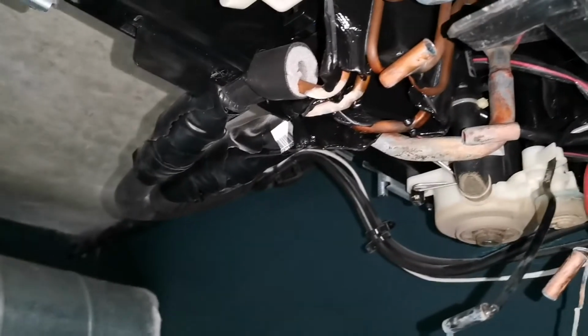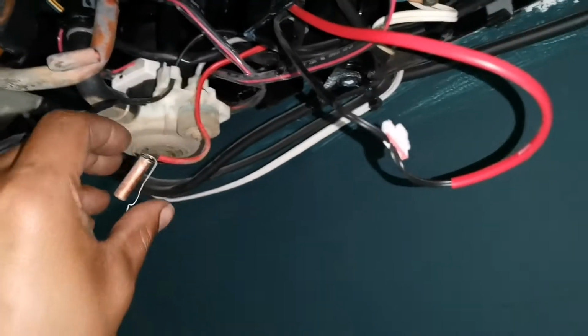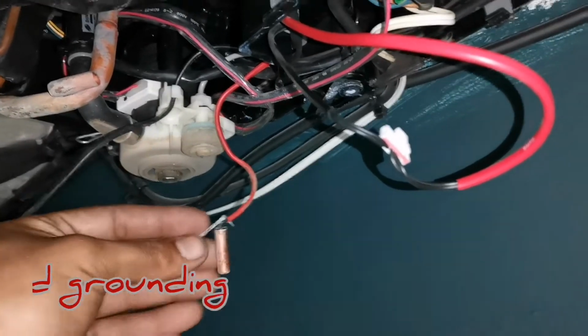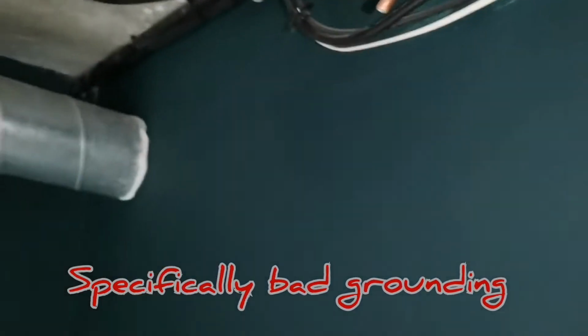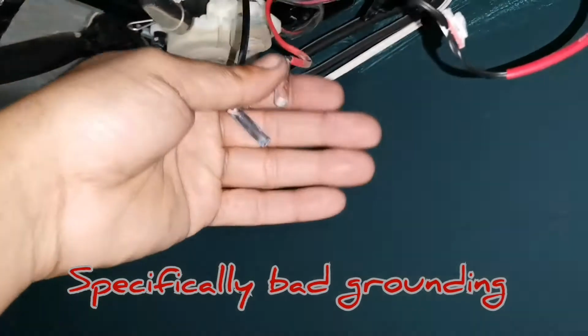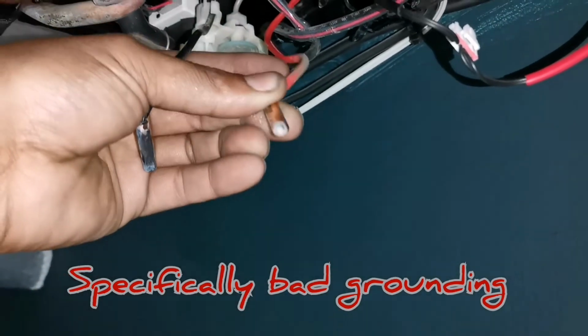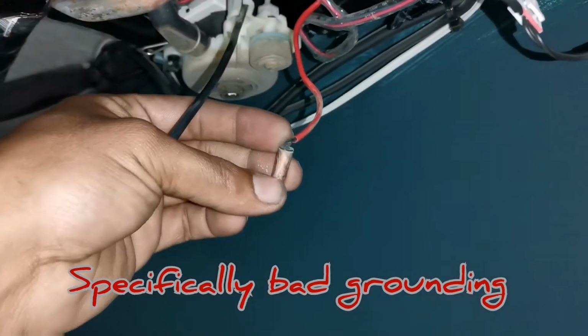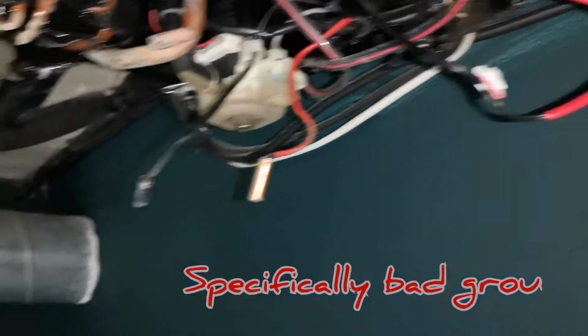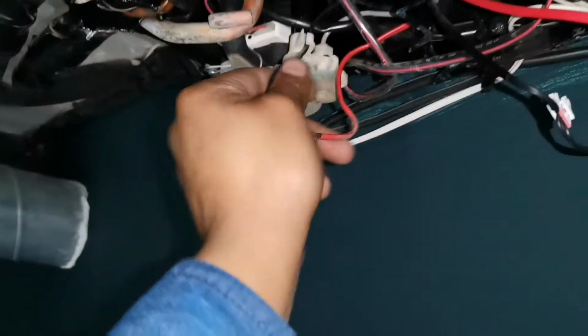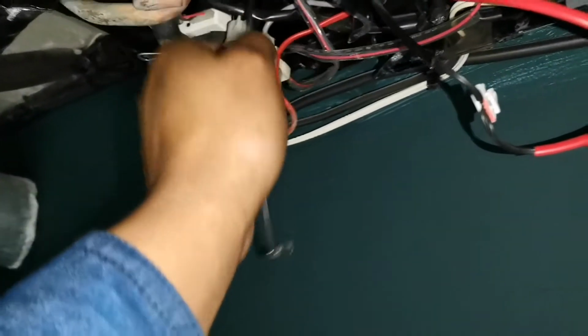So it's voltage related problems, so voltage spikes, those kind of things, because you'll notice that it's always the pipe sensors, the one with the copper end, that ends up being damaged. So that's why these sensors fail so often.